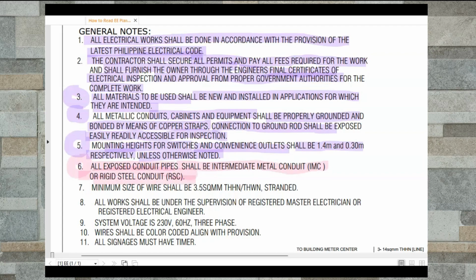Kung ang pipe mo ay nakabaon o embedded sa soil o sa slab, pwede mong gamitin ang PVC or polyvinyl chloride. Number 7, importante ito: minimum size of wire shall be 3.5 square mm THHN or THWN stranded. Kung nakasulat na stranded, tapos 3.5 yung minimum wire, dapat sa on-site installation wala kang makitang wire na mas mababa pa dyan.